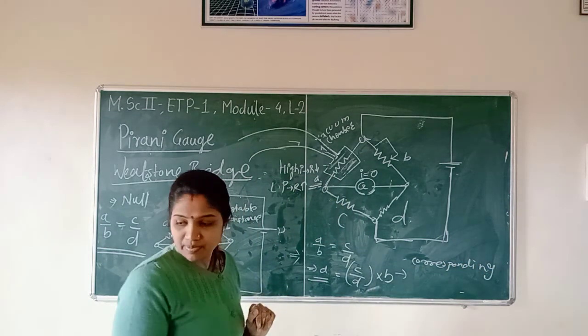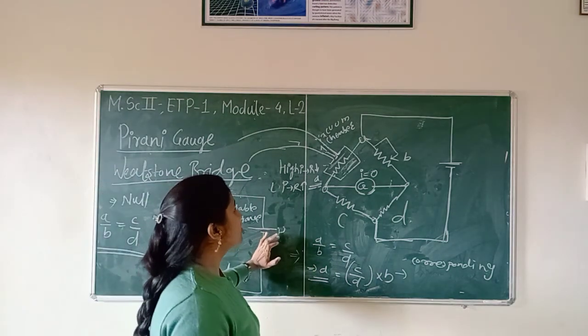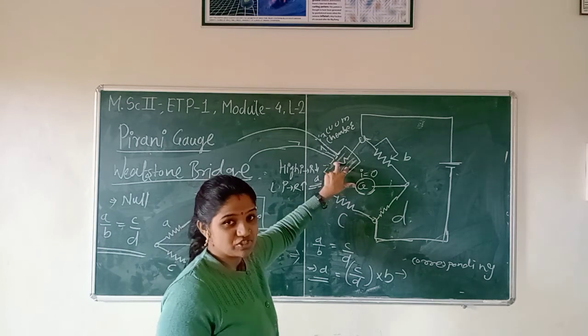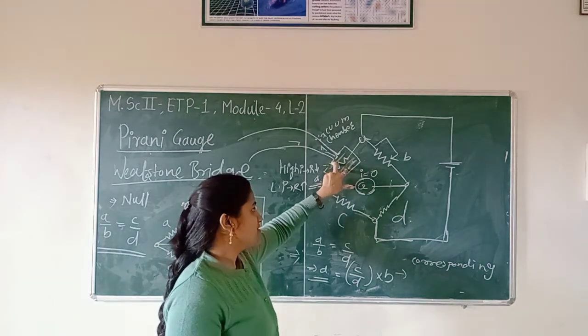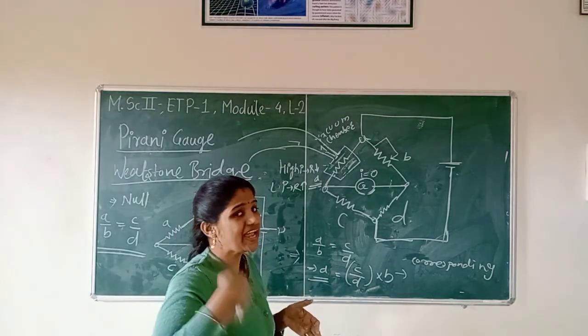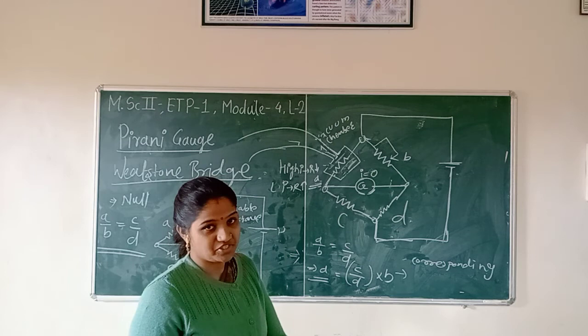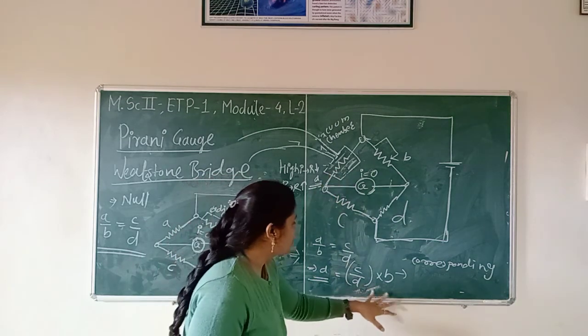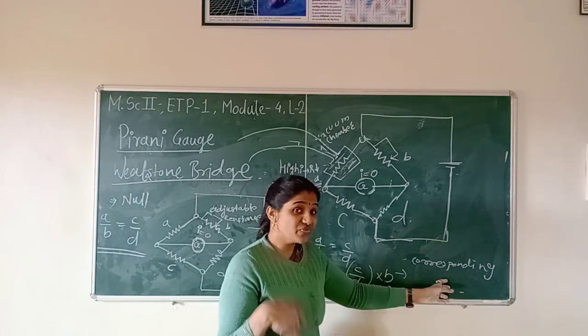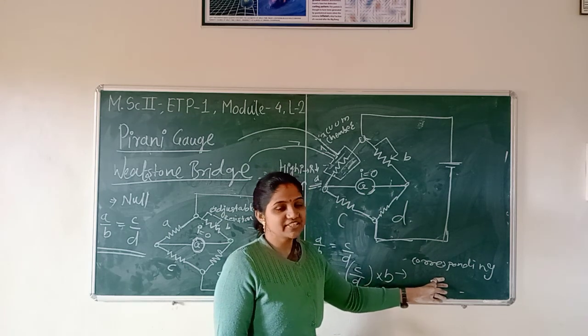Corresponding pressure value. But there is another disadvantage. For every gas, whether it is nitrogen or any other, we have to do a separate calibration of resistance against pressure. How much resistance we have found and the corresponding pressure, which means we have to continuously calibrate all that. Okay, this is a disadvantage.